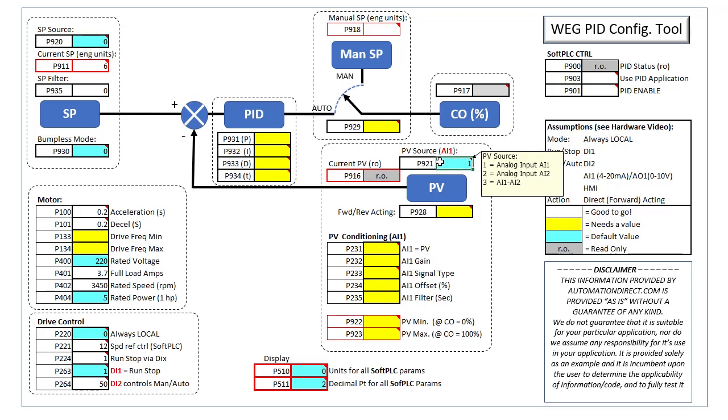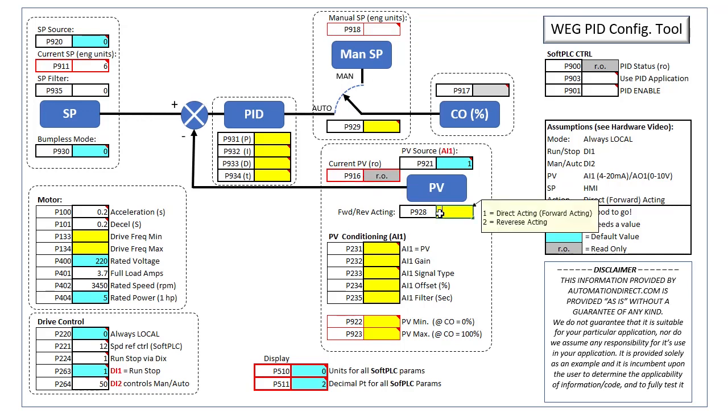Let's configure the process variable. Parameter 921 is where we tell the PID app that the process variable is coming in on analog input 1 and you can view the current process variable at any time in Parameter 916. We have a direct or forward acting system, so we put a 1 here.